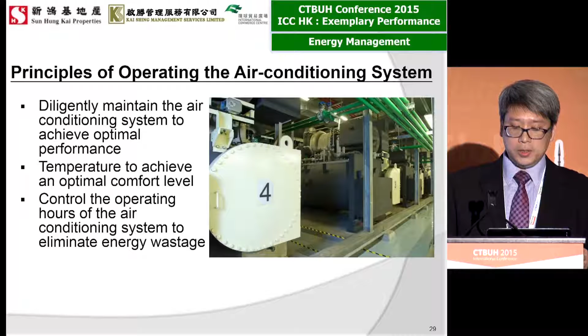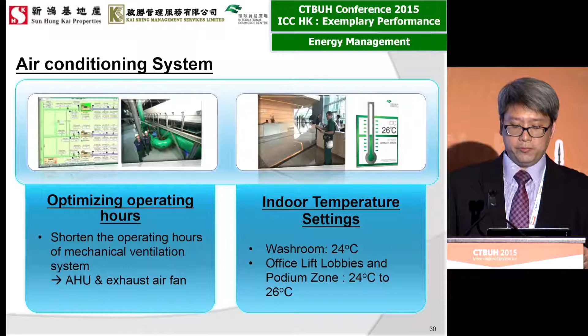We shorten the operating hours of our AHU and mechanical fans in line with our tenants' business hours, without ignoring the real demand. Given that 1 degree Celsius higher indoor temperature can result in 3% electricity saving, the indoor temperature of some common areas is set between 24 to 26 degrees Celsius, achieving a balance between thermal comfort and energy conservation.